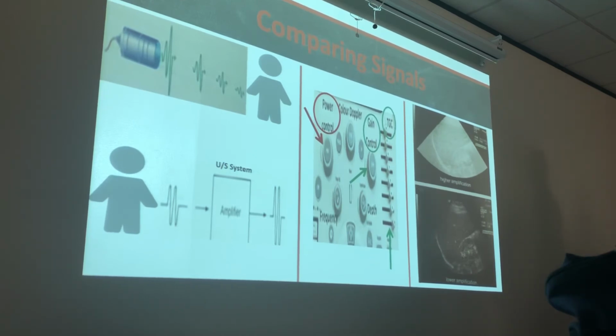But we said we can't change the power, because the power is fixed by the manufacturer. Right, but we're changing the acoustic power. As far as the power coming from that transducer, that's already fixed. But you can adjust the system acoustic power, as far as the power that the machine is putting out or not putting out. So that is a button that is adjustable on the machine. All right, we're good here, guys?